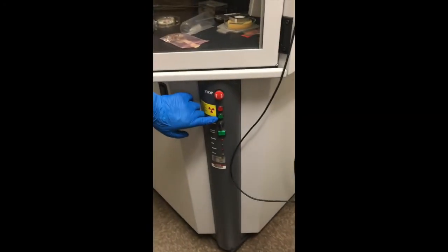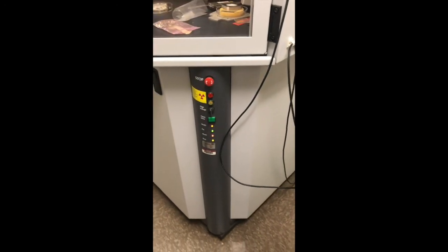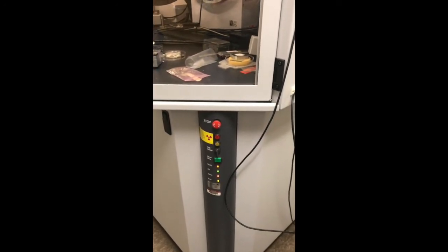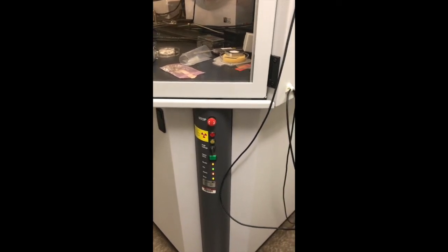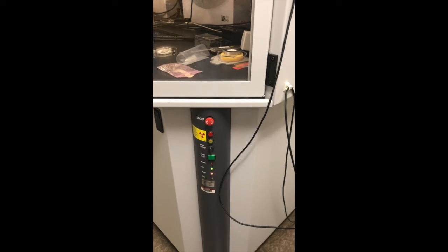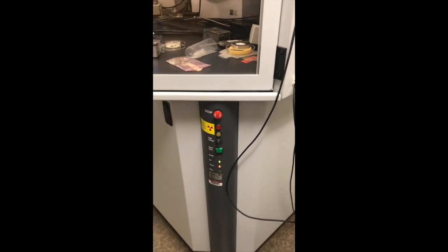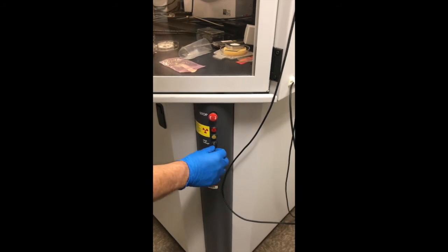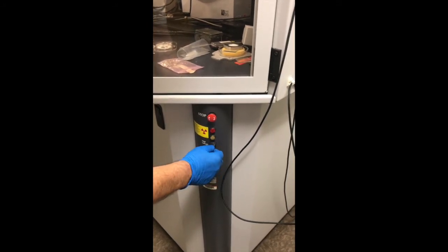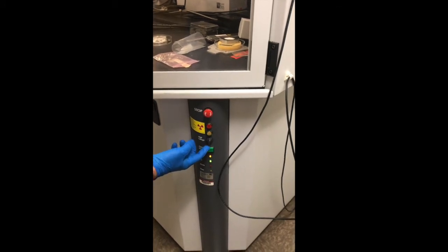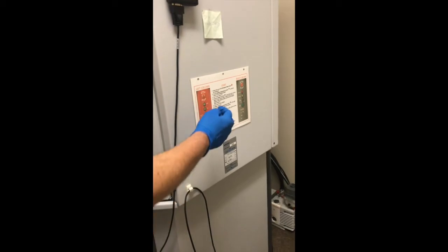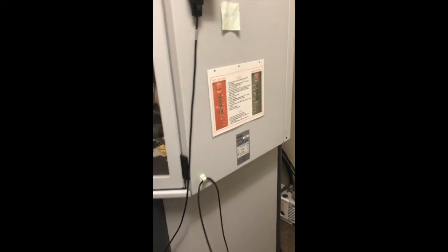It's going. Okay. So next thing we do is to turn the power on, which is this button right there. Right, and then wait. Then 2 lights will come on. So several seconds, and then these lamps come on. Then now we'll turn on the high voltage and use this knob. Okay, turn it clockwise about 45 degrees. Hold it there. All right, and then those 2 lamps come on, and you can let go. So now we have high voltage on, and the process is explained how to turn the high voltage on right here on the side. Okay, stop.